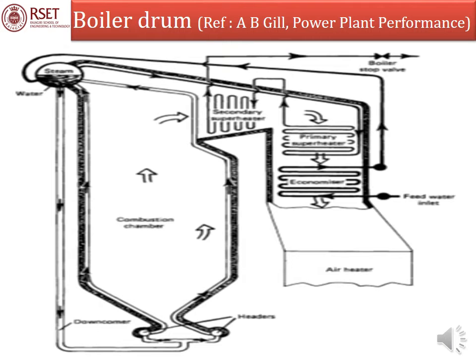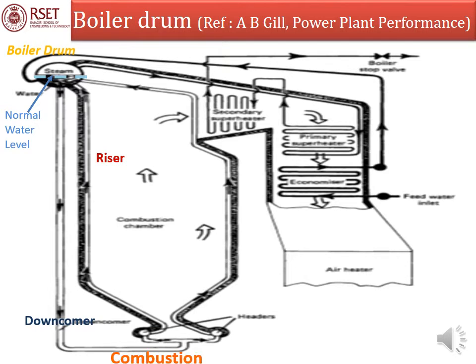This is a typical boiler drum arrangement. We can see the boiler drum, and this is the water level to be maintained — the normal water level, NWL. Below the drum is the downcomer, a tube through which water comes down. On the right side is the riser tube, through which water that has come down through the downcomer rises because of heat from the combustion chamber.